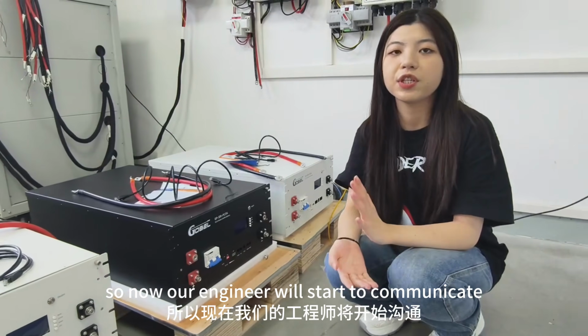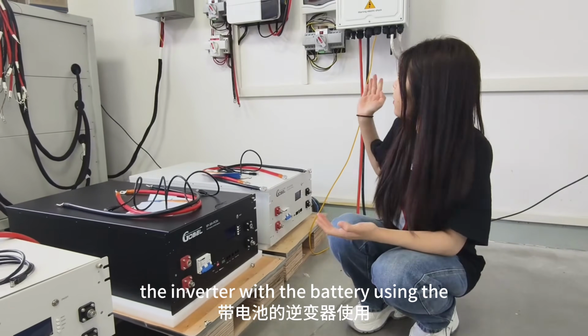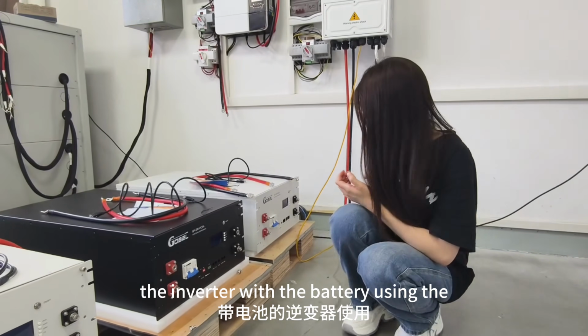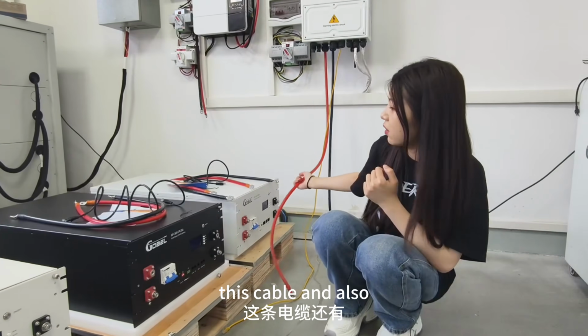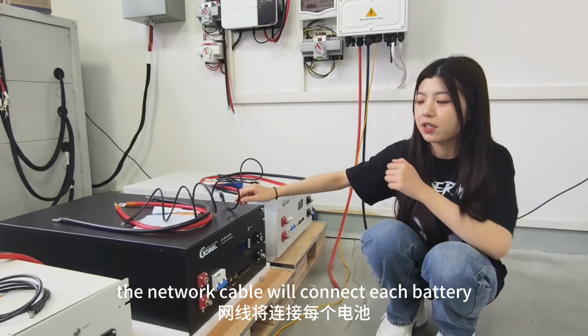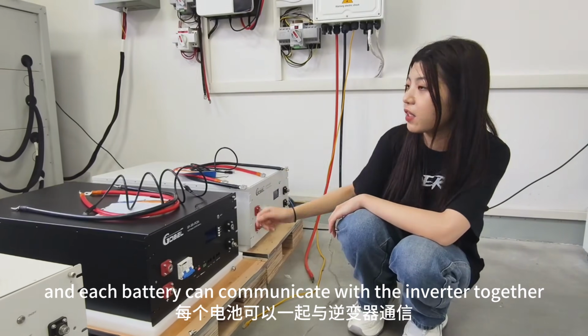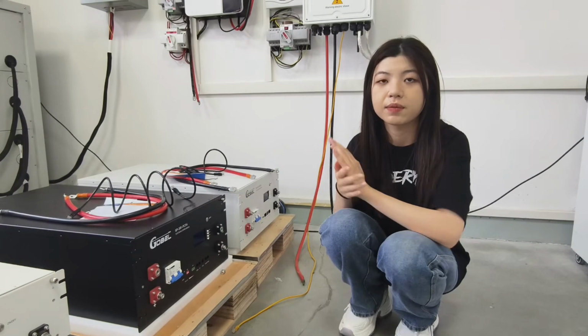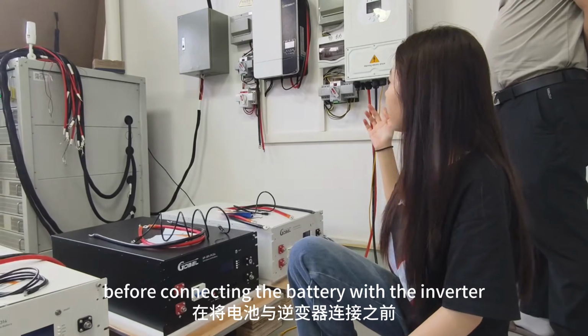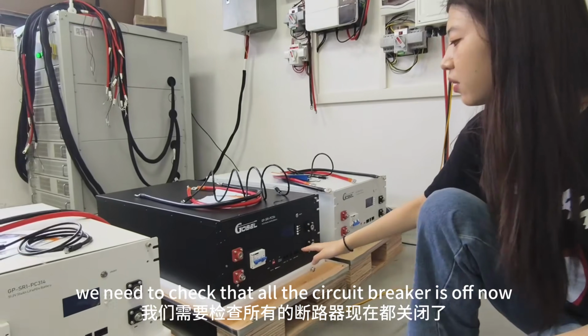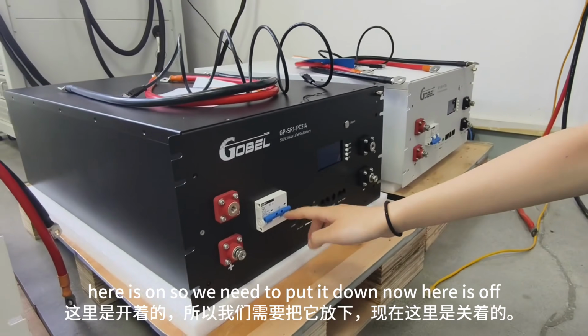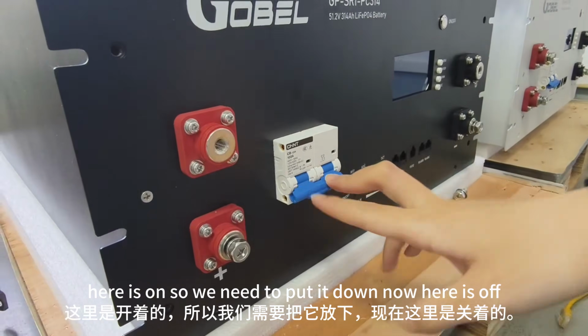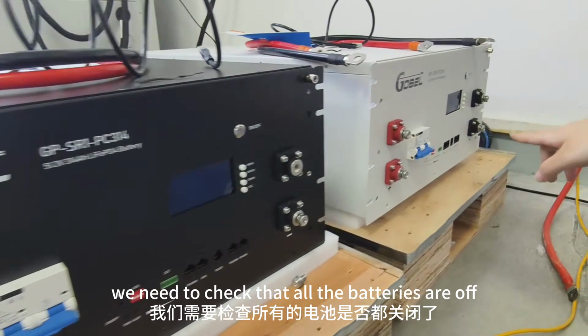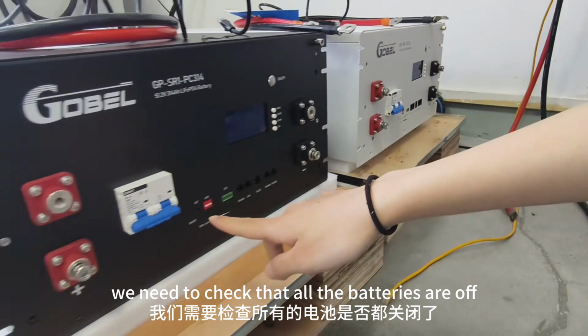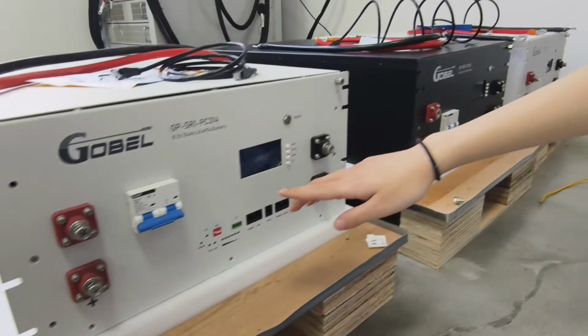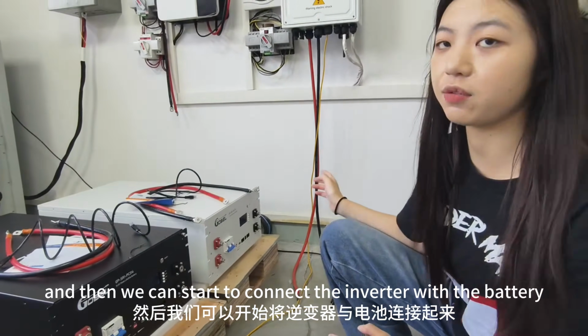Now our engineer will start to connect the inverter with the battery using this cable, and the network cable will connect each battery so each battery can communicate with the inverter together. Before connecting the battery with the inverter, we need to check that all circuit breakers are off. Now here is on, so we need to put it down. Now it's off - we need to check that all the batteries are off, then we can start to connect the inverter with the battery.